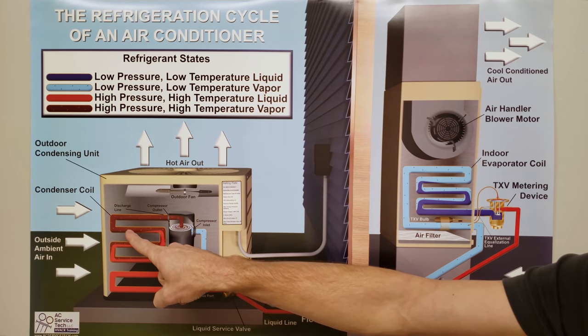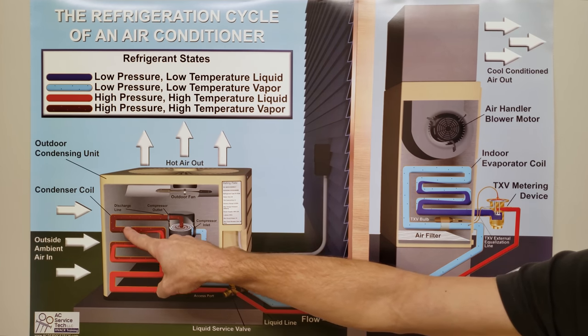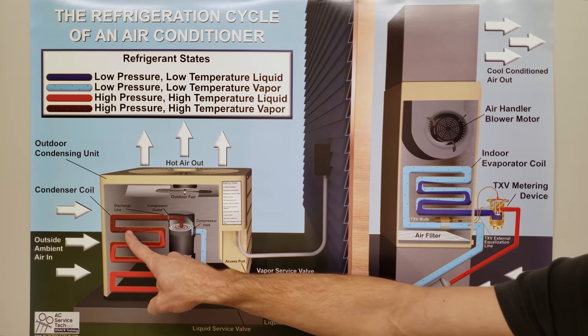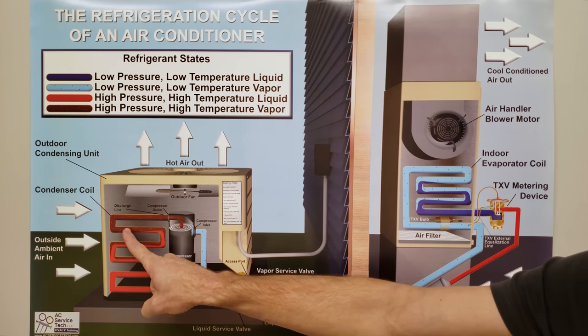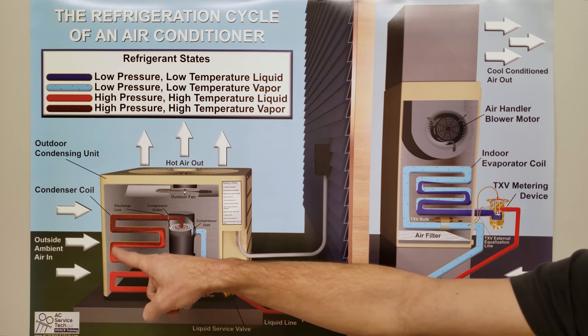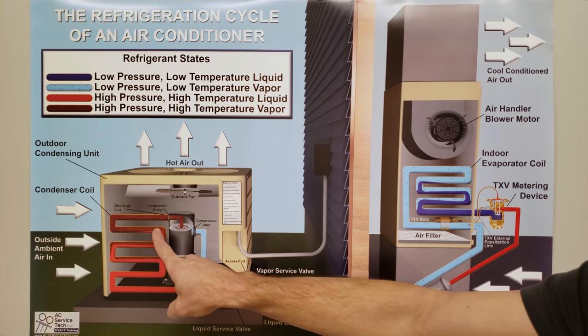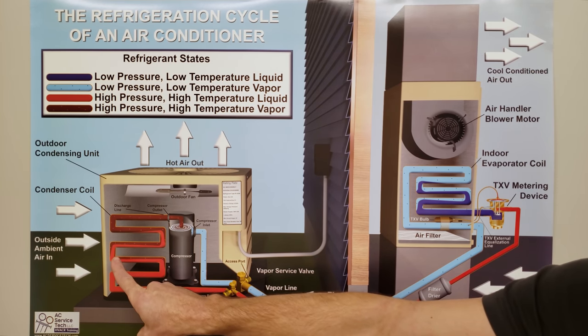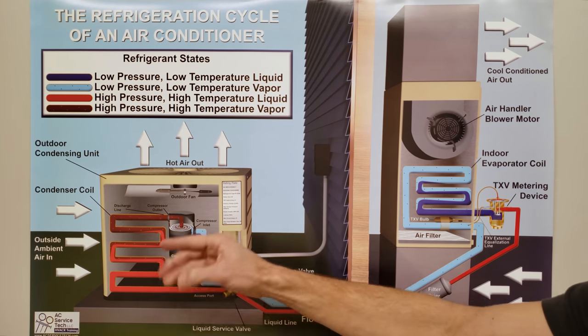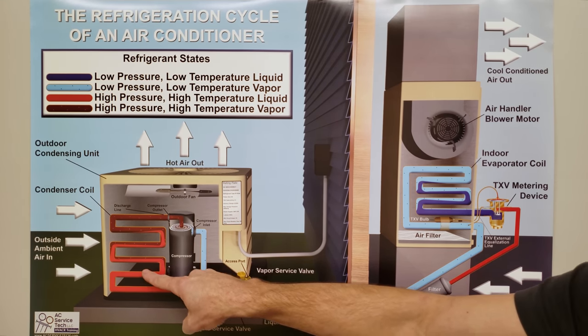Now at 170°F, the refrigerant travels through the condenser coil and rejects its stored heat into the outdoor air. As it rejects heat, it lowers in temperature until liquid begins forming alongside vapor — that's the saturated state in the condenser. Once saturated, the refrigerant stops lowering in temperature but continues rejecting heat. So it stays at 105°F throughout the saturated region of the condenser coil.